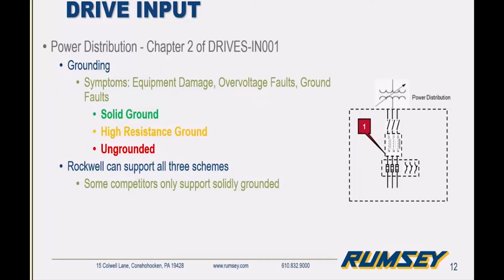Okay, moving on the input here, we want to make sure we determine what the actual grounding scheme is of the power distribution, right? So we want to determine what type of grounding is actually being used. Rockwell is kind of unique in the fact that it can actually support and operate on multiple different grounding schemes. For example, here, a solidly grounded system. It can also accommodate high resistance ground and ungrounded systems. Not all other manufacturers can actually do that.